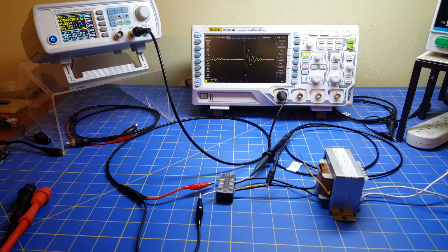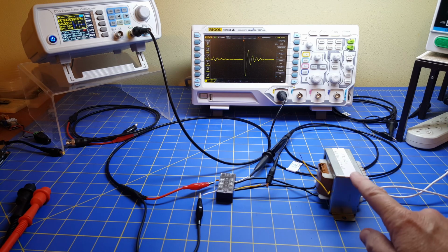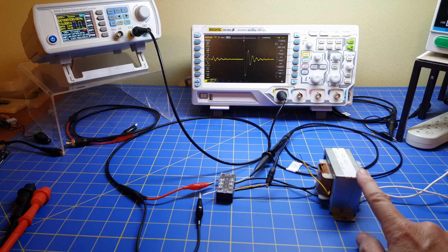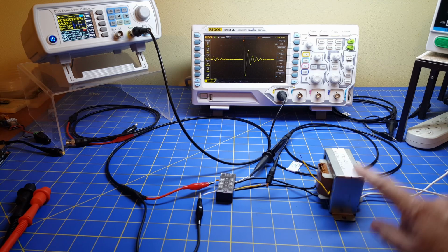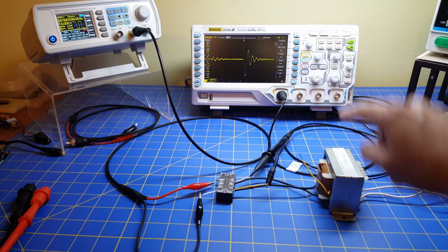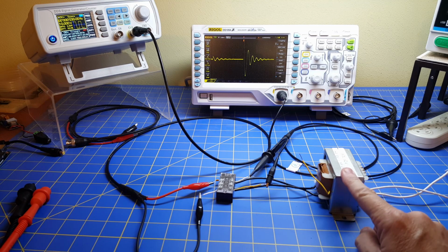Okay, so welcome back. This is part three in our series where we discuss the concept of a ring tester. The purpose of a ring tester, as we discussed in the previous videos, is to test a transformer to see whether it's good or bad. As you can see here on our bench, we have a transformer and we're applying a pulse of voltage, a square wave, and the result is this ringing oscillation of the voltage across the transformer.